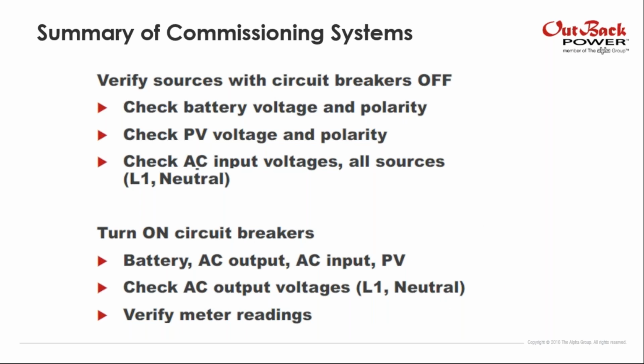Now, as a summary, first, we need to verify sources with circuit breakers off. I mean that there is no power anywhere. Check battery voltage and polarity, then check PV voltage and polarity, and then check AC input voltages in all sources. I mean in hot line and neutral. If I have the grid, if I have the generator or whatever.